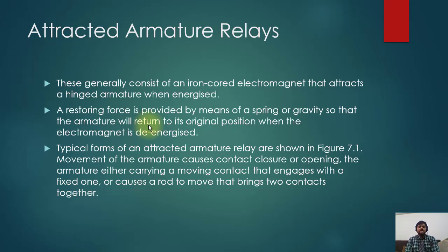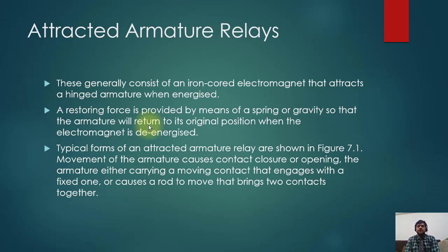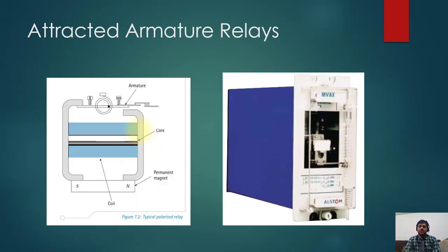Attracted armature relays generally consist of an iron core electromagnet that attracts a hinged armature when energized. A restoring force is provided by means of a spring or gravity so that the armature will return to its original position when the electromagnet is de-energized. Movement of the armature causes contact closure or opening — the armature either carries a moving contact that engages with a fixed one, or causes a rod to move that brings contacts together.